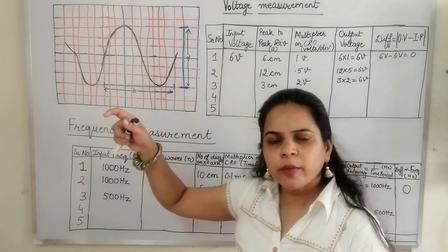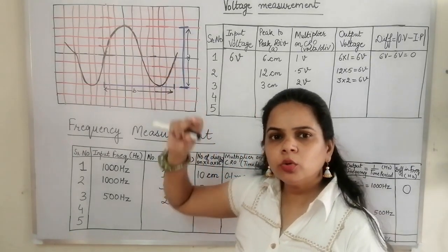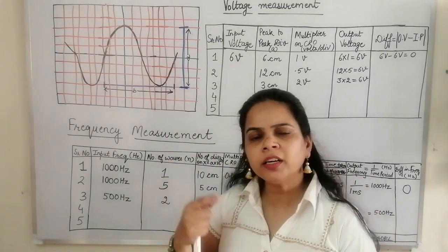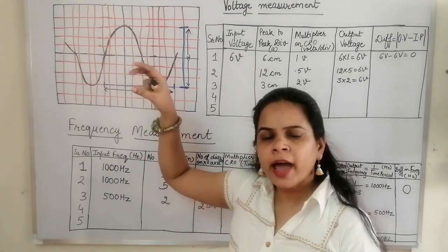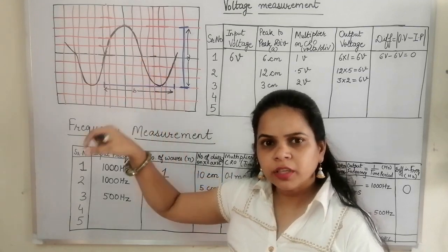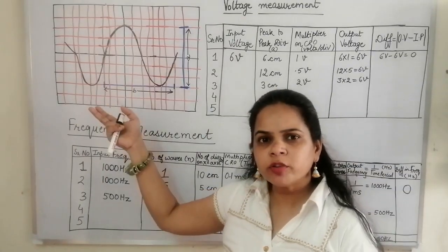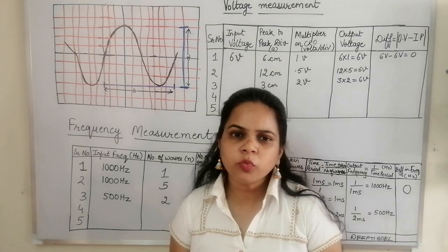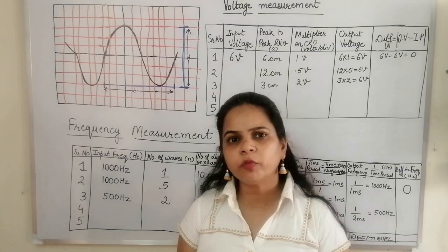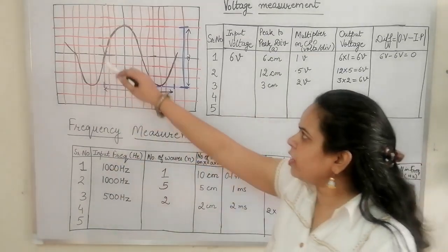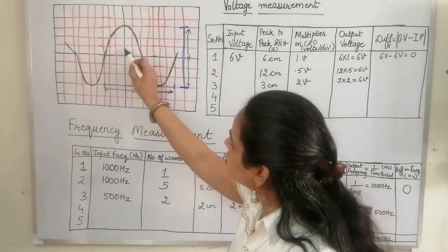Using the X position and Y position, we can adjust the positions of the wave, and using the voltage amplifier and the time amplifier, we can adjust the wave. Either we want an amplified wave, or a little less magnified wave, we want one wave, or we want 10 waves on the screen. That is up to us. So we can select the knobs and adjust the number of waves and the height of the amplitude of the wave accordingly. Supposing we have this type of wave, as I have already discussed, this is one block.